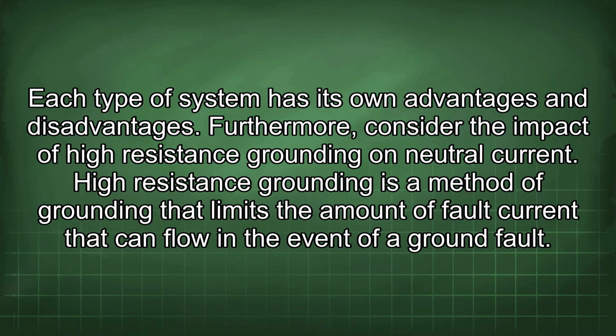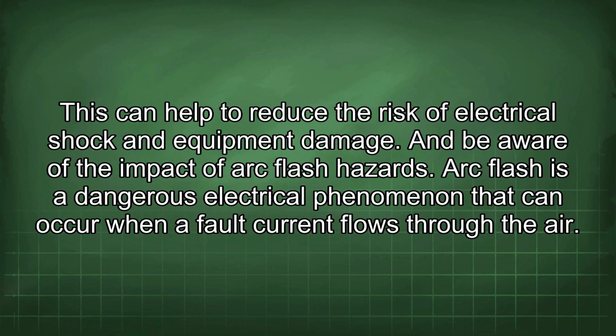Furthermore, consider the impact of high-resistance grounding on neutral current. High-resistance grounding is a method of grounding that limits the amount of fault current that can flow in the event of a ground fault. This can help to reduce the risk of electrical shock and equipment damage. And be aware of the impact of arc flash hazards. Arc flash is a dangerous electrical phenomenon that can occur when a fault current flows through the air.